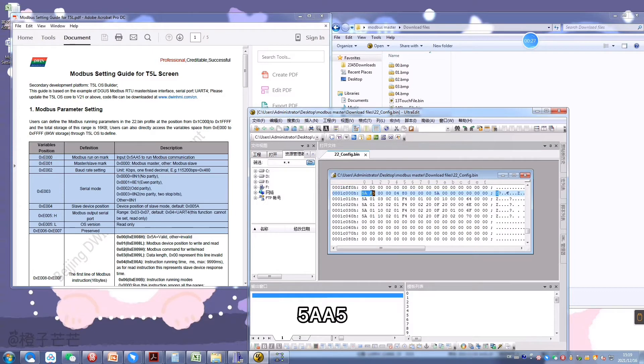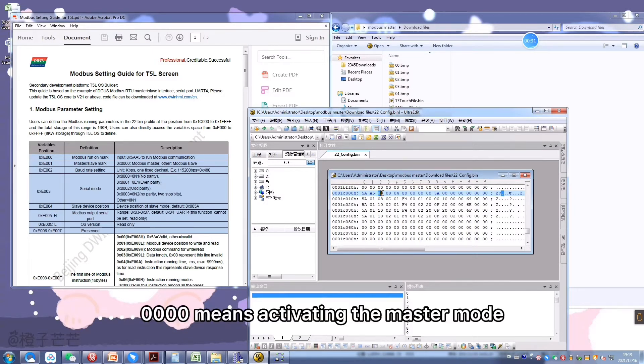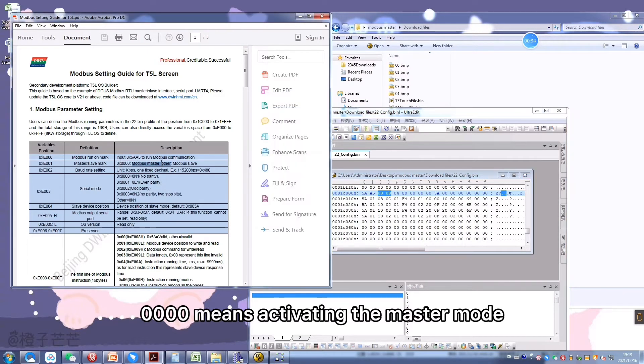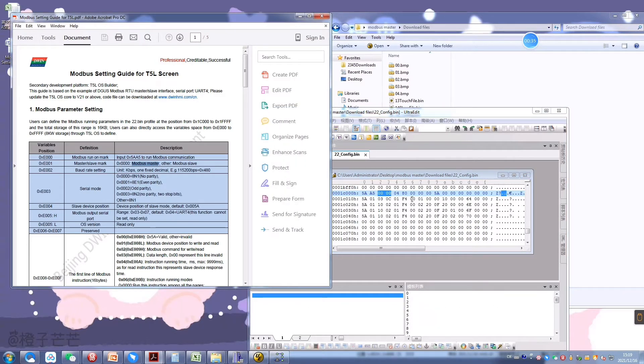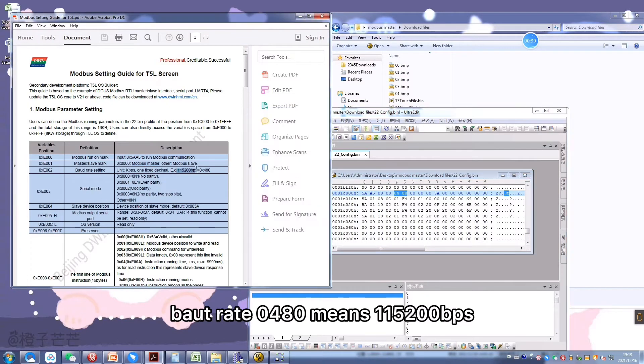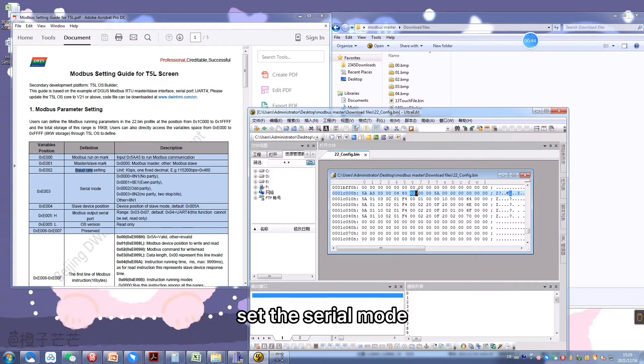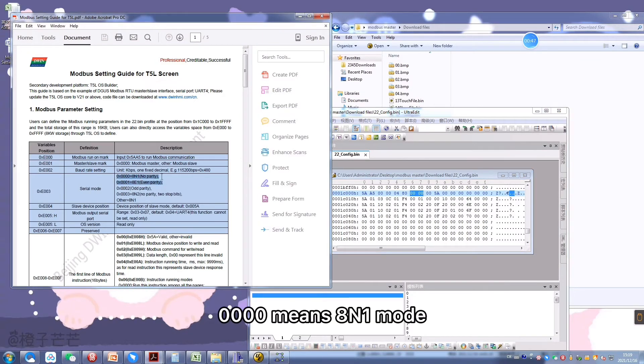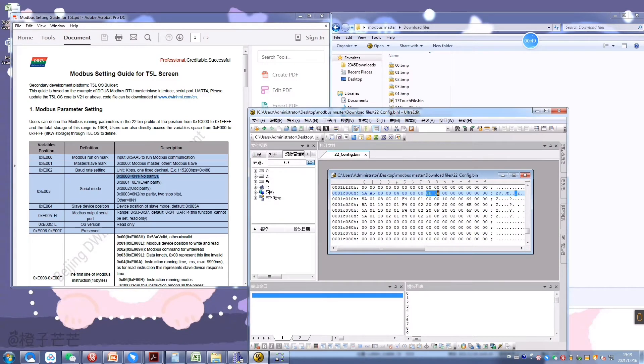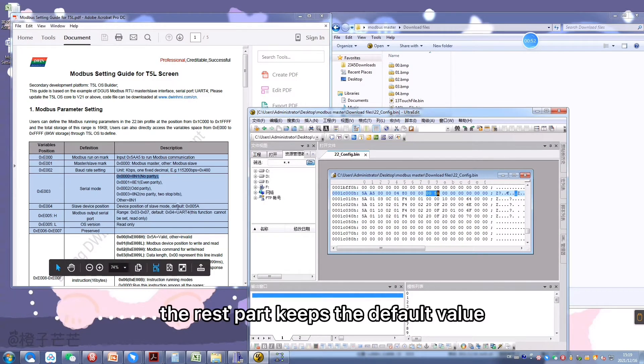5AA5 is to activate the Modbus communication. 4 zeros means activating the master mode. Baud rate 04 is for 115,200. Set the serial mode - 4 zeros means 8N1 mode. The address of the slave. The rest part keeps the default value.